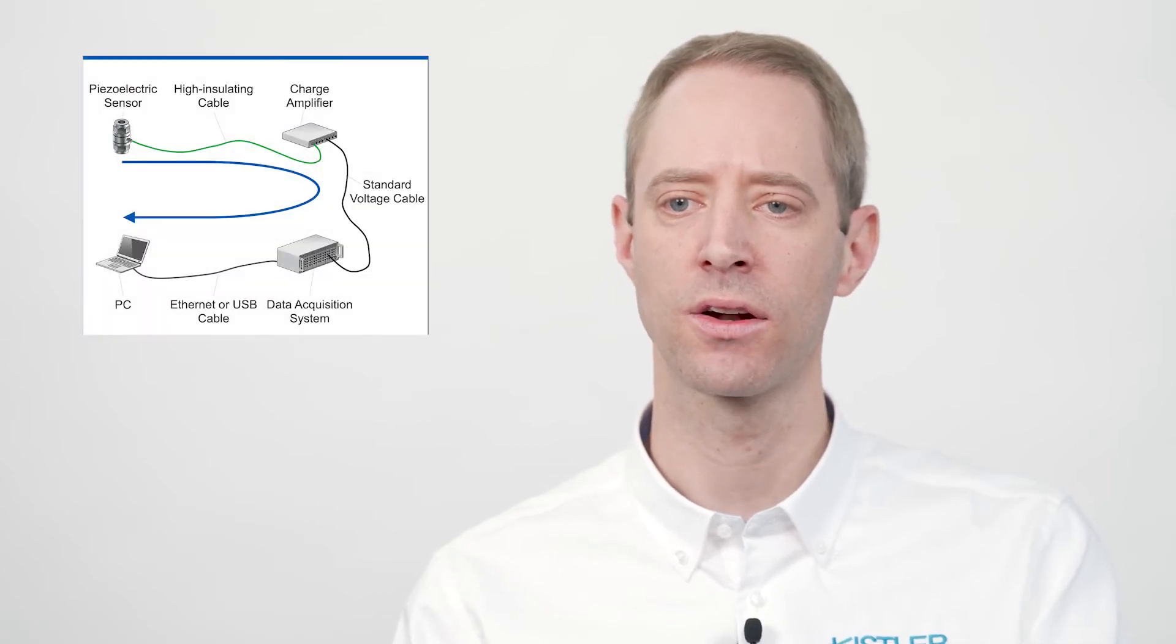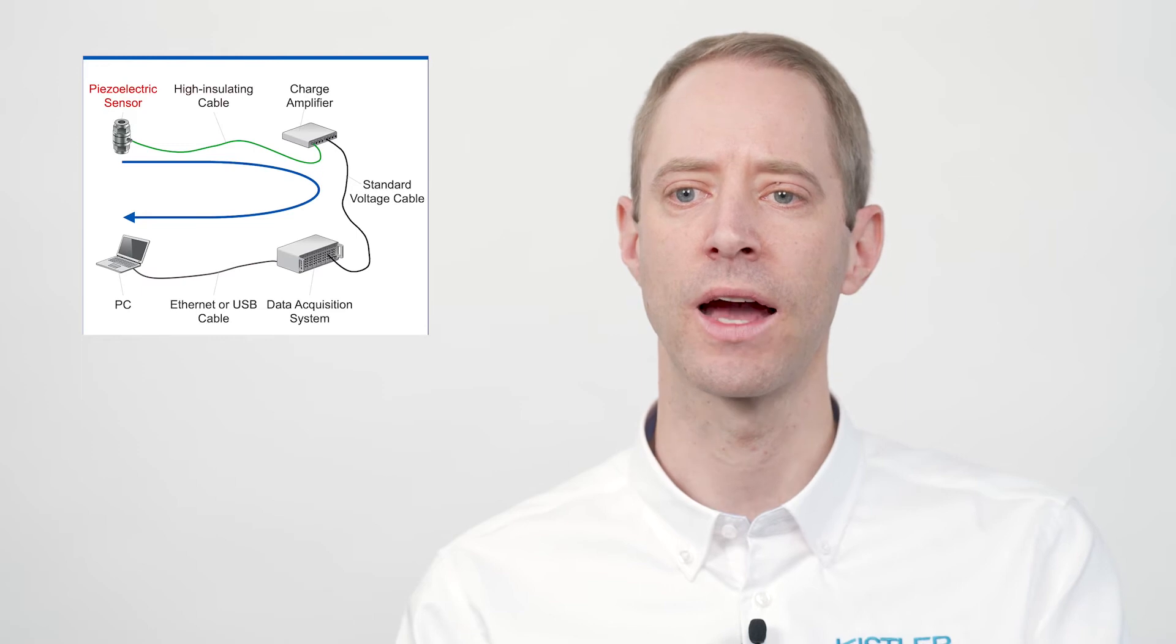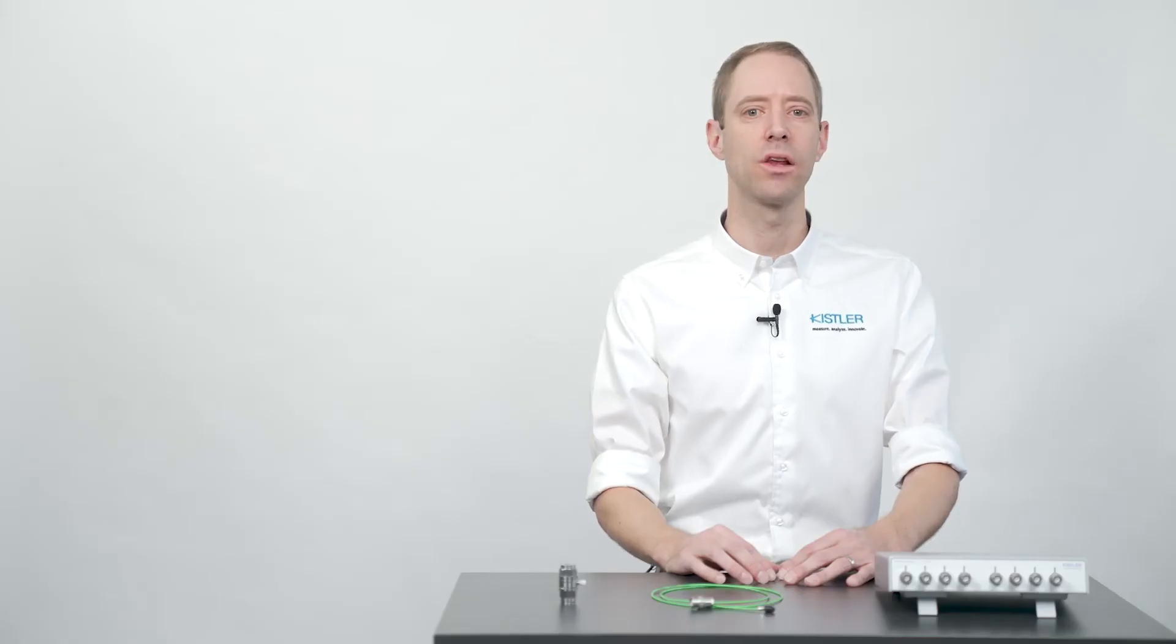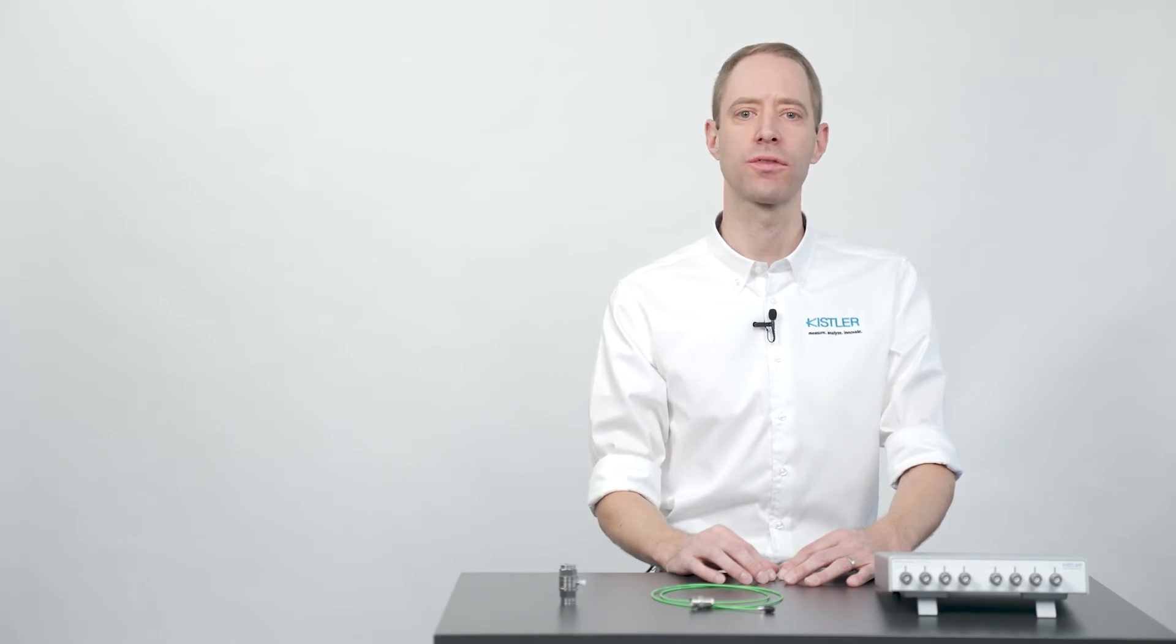So, what are potential sources of drift in a piezoelectric measuring chain? Since drift is a parasitic current, only components where a charge signal is generated, transferred or processed can contribute to drift. Specifically, these are the piezoelectric sensor, the high insulating cable and the charge amplifier. Let's take a look at the potential sources of drift for each component.